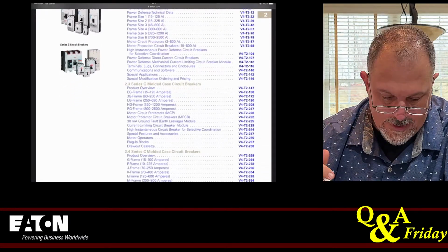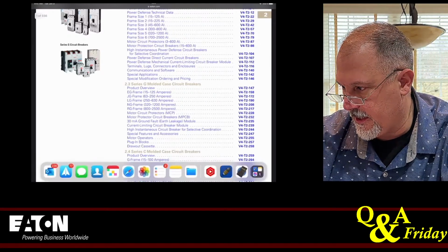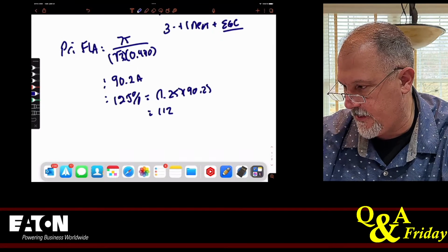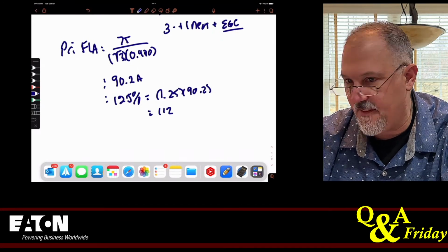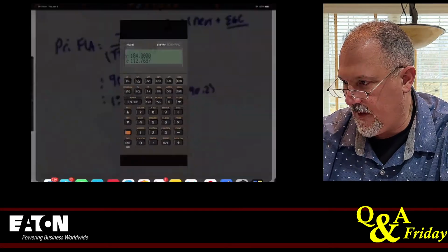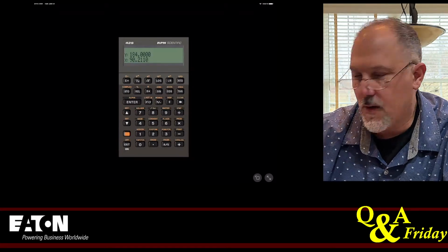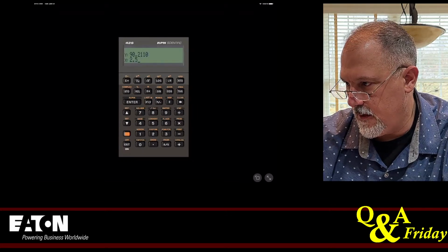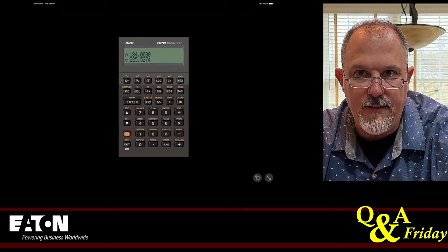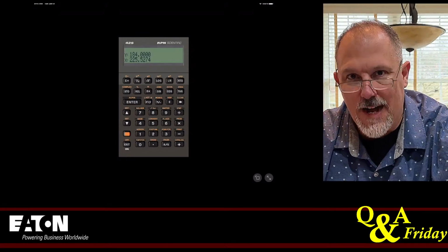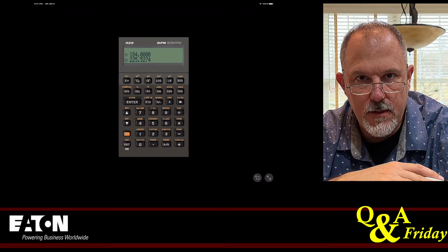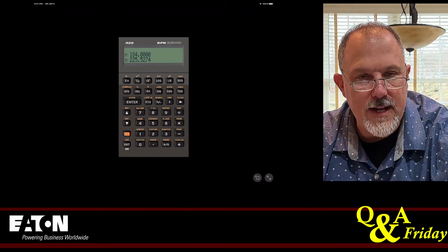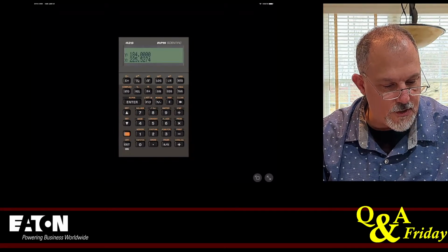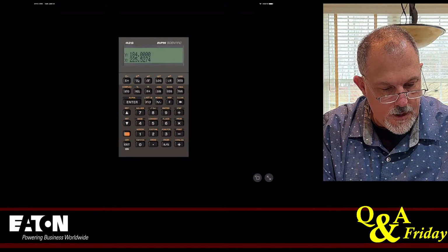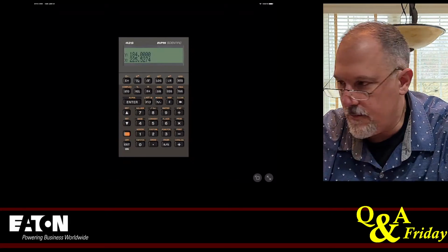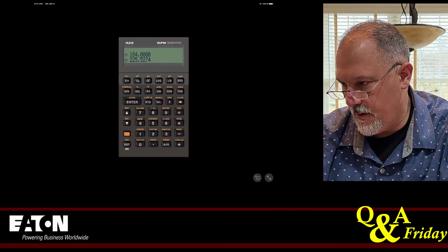Now we have to look at what the breaker size was on the secondary. 112. We were talking about anything greater than 112, right? Because that's only at 125%. Remember, I can go up to 250%. So at 90.2, I can go up to a 225 amp breaker. I can't go greater than 225.5, so I can go at 225 or less. I can't go to the next higher because 250% is the maximum size based on the tables, right? There's a note 3. I can't go any higher than that. That's an important thing to remember.